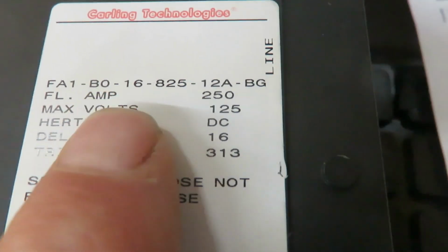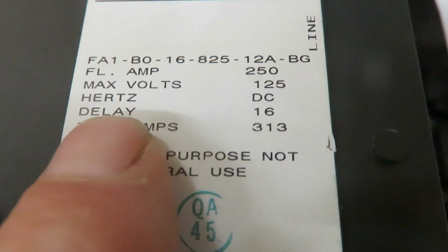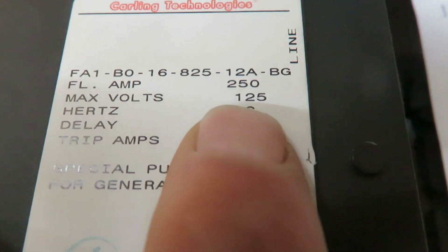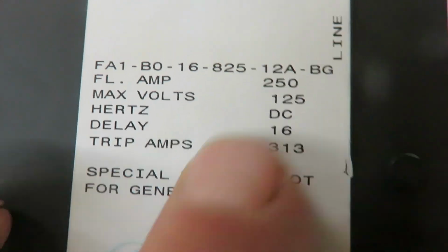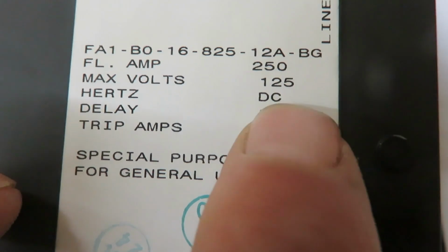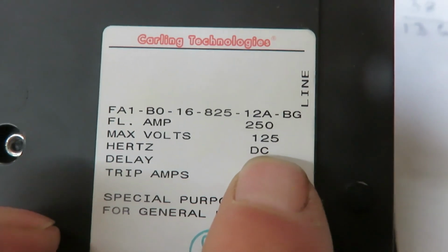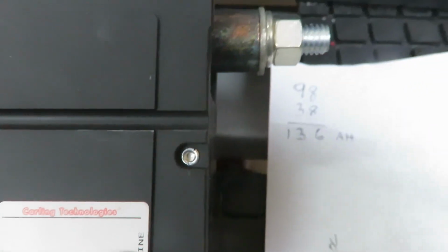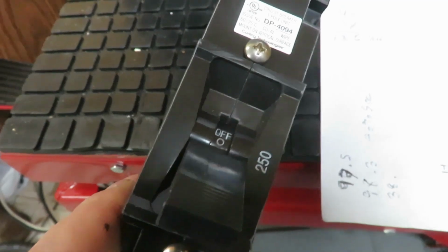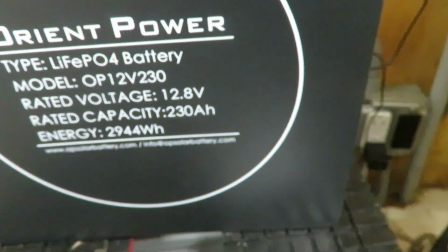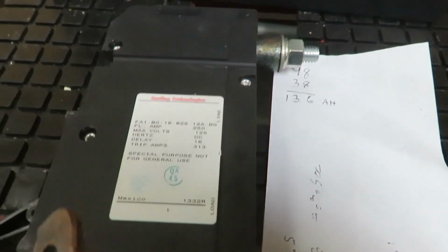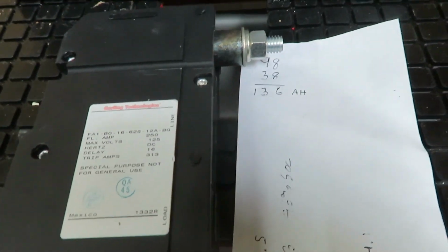This breaker is rated for 250 amps and the maximum volts is 125. You can see the hertz rating is DC, so it's not an AC breaker. It's labeled line and load at these terminals - I think they're non-polarized, but that's how they labeled them. It's a real big giant breaker for an inverter, this has a 200 amp load. So you could use this breaker as long as you size your cable big enough.